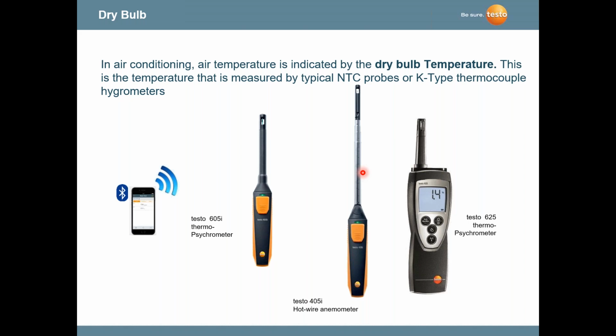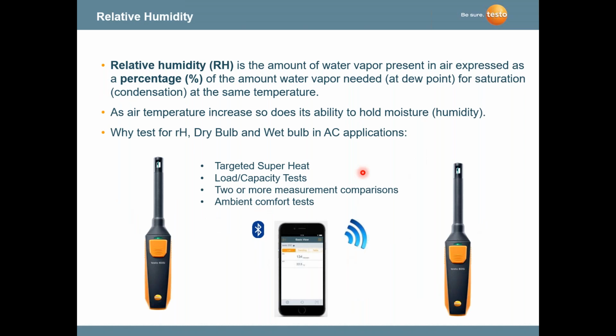Before we get into superheat and subcooling, I just want to go over a few definitions. One definition that we use in HVAC is dry bulb. Dry bulb is just ambient air temperature. We use NTC probes and K thermocouples to measure dry bulb. In HVAC, we have a lot of terms that mean kind of the same thing, but dry bulb is ambient air temperature. Relative humidity is the amount of water vapor present in air. We measure relative humidity on almost every job we go to. It's not only for customer comfort, it's also for looking at targeted superheat, capacity tests, or relative humidity comparisons in a building.